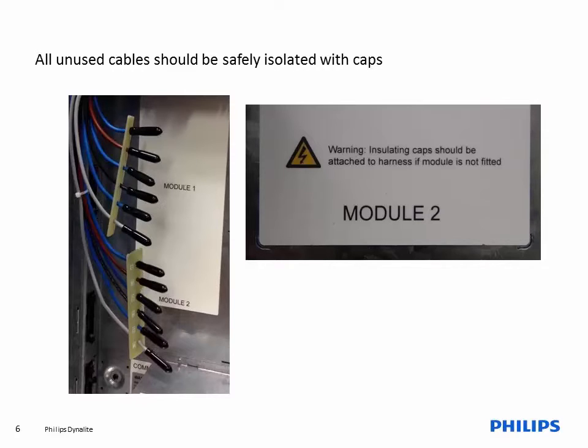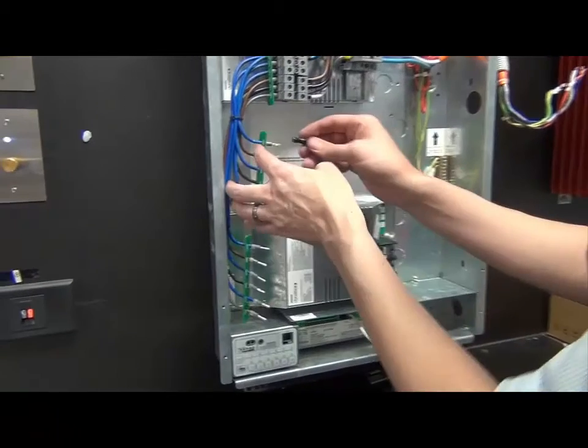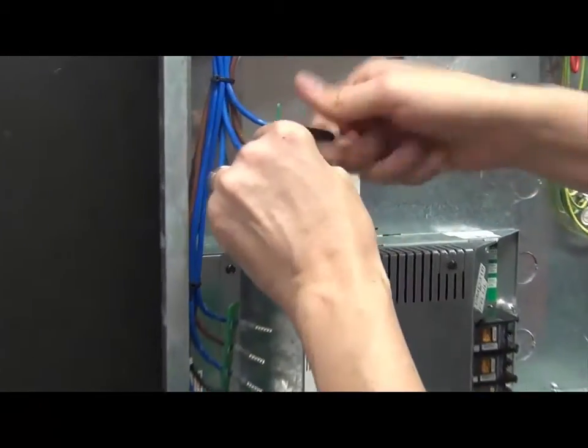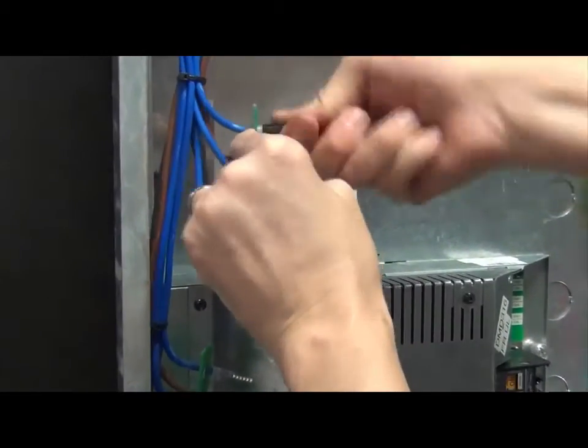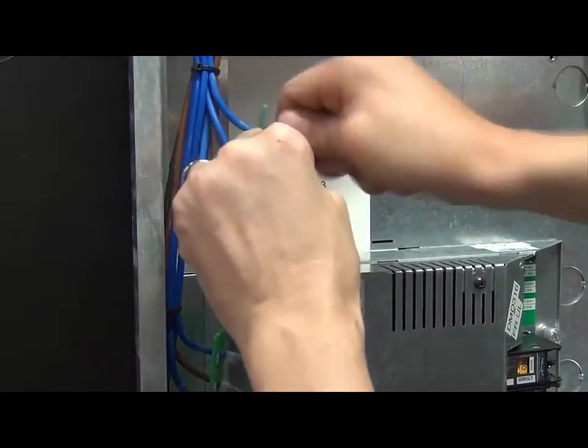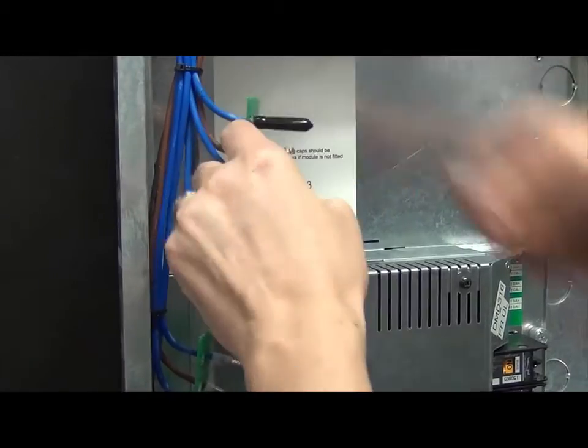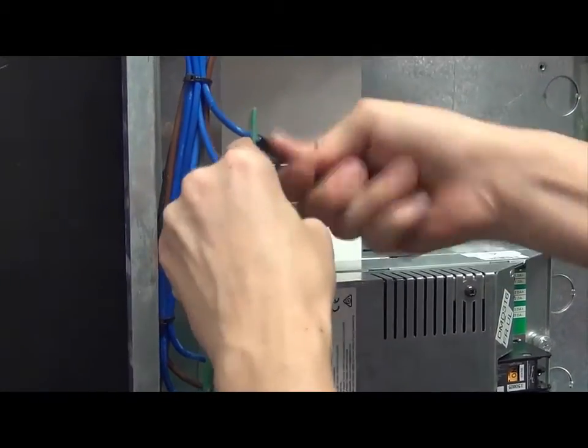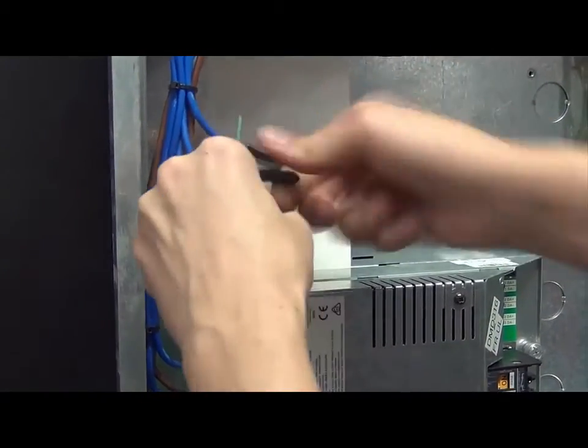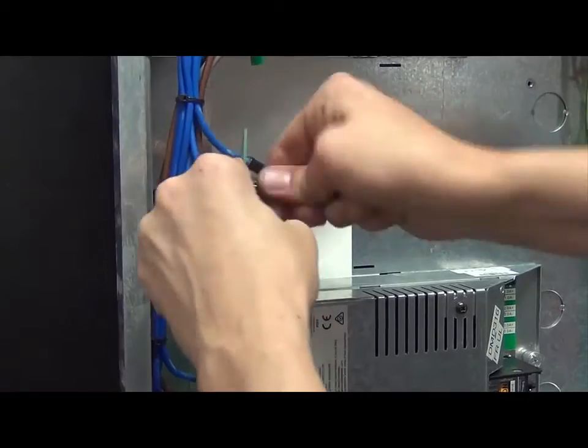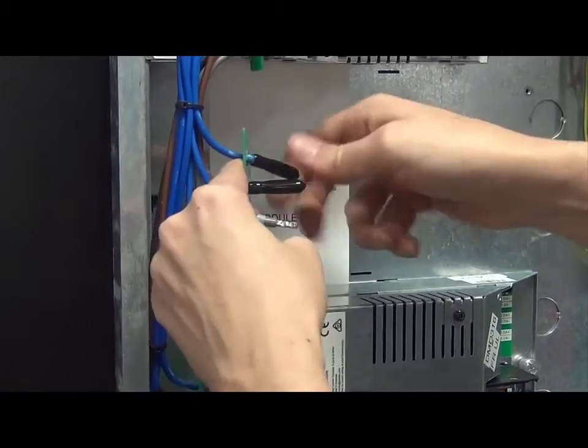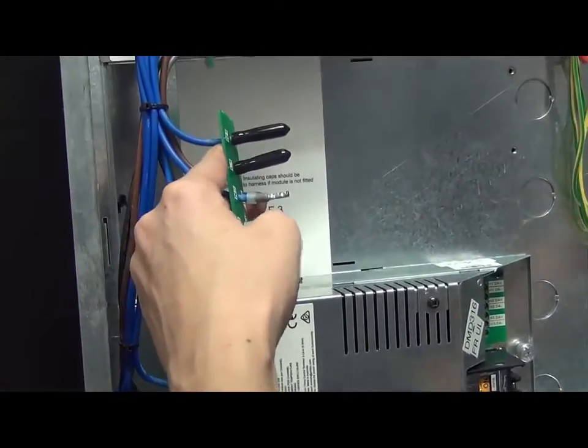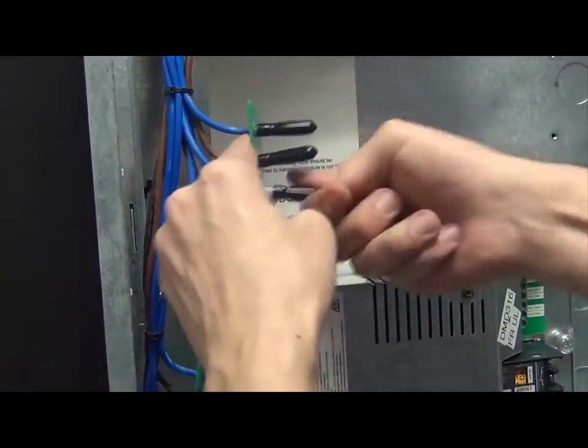Please refer to the accompanying documentation or distributor's website for further information. For each exposed cable, twist on an insulating cap. Ensure that the cap covers the entire terminal including the white spacers on the cable. The cap should go all the way down to the PCB. Each cap should be tightly attached.